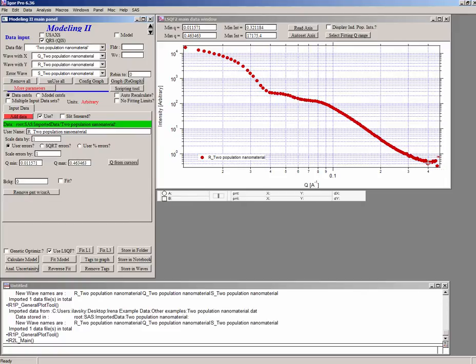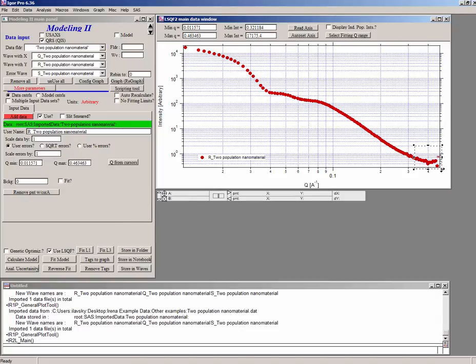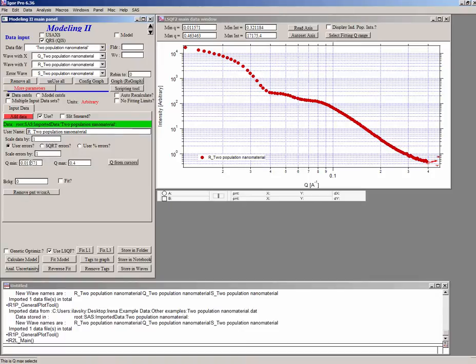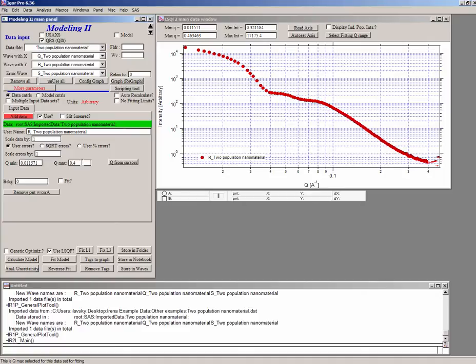Now we can immediately look at it and say what are we going to do with the Q range we're going to model. Obviously, if you look on this area here at high angles, the data are coming down and then they're coming flat and they're going to come again. I believe anything above 0.4 is probably not very useful. And you can use the choices out here in this area, Qmin and Qmax, to select a fitting range. There are various ways to do that. We may actually do it a little bit later with other ways.